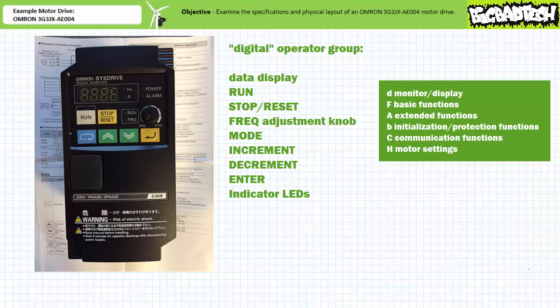In addition to the data display, the digital operator group includes several indicator LEDs. The power LED is lit when the motor drive is powered up. The alarm LED is lit when the motor drive experiences an error. The run LED is lit when the motor drive is actively accelerating, running, or decelerating a motor. The program LED is lit when parameters of the motor drive are being adjusted. The hertz and amp LEDs are lit to accompany numerical data displayed on the data display with the appropriate units.